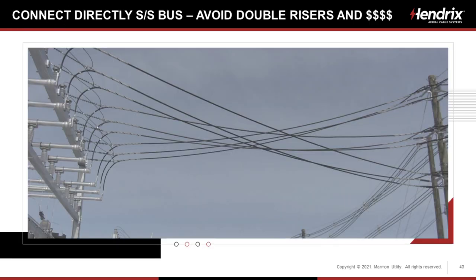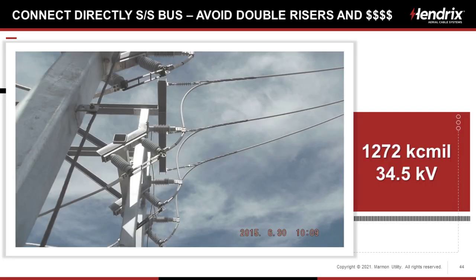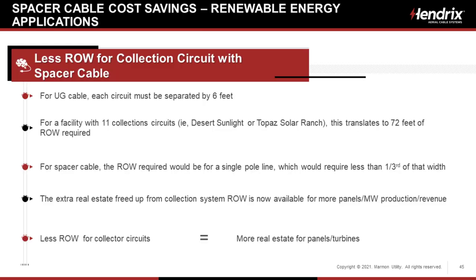And if you take a look at that, here's a job we did years ago. You can see we're coming off the last pole. We dead ended at the last pole outside the substation fence and just simply ran a slack span over to the substation bus. Nice, economical, and simple. Here we ran it right to the switch at the substation bus.